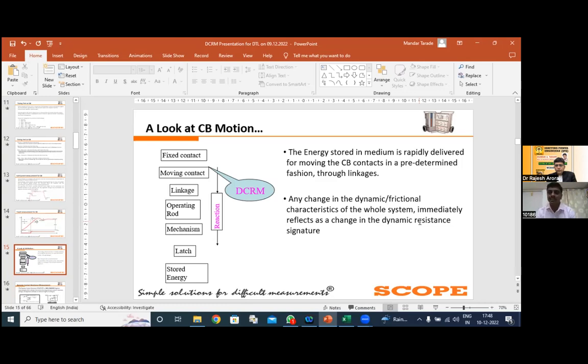Okay, so the electrical stroke length is always mentioned on the transducer. Before performing the operation, at the time of preparing the setup, we need to feed the electrical stroke length as well as the linkage ratio. If we properly feed the electrical stroke length, then we will get the proper value of the mechanism travel, that means the total travel. And if we feed the linkage ratio properly, then we will get the proper value of the contact travel.